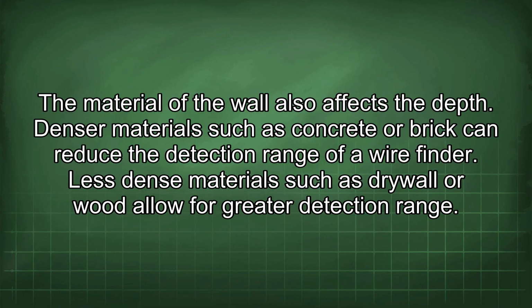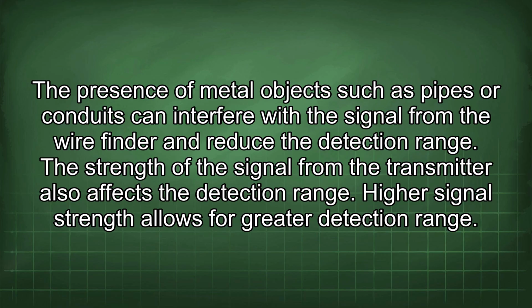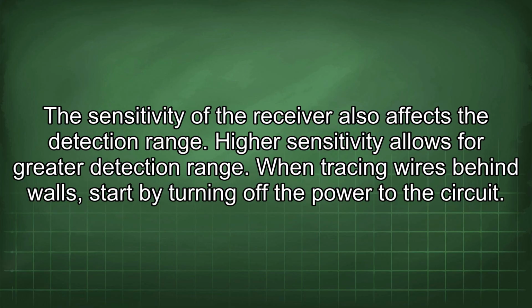The material of the wall also affects the depth. Denser materials such as concrete or brick can reduce the detection range of a wire finder. Less dense materials such as drywall or wood allow for greater detection range. The presence of metal objects such as pipes or conduits can interfere with the signal from the wire finder and reduce the detection range. The strength of the signal from the transmitter also affects the detection range. Higher signal strength allows for greater detection range. The sensitivity of the receiver also affects the detection range. Higher sensitivity allows for greater detection range.